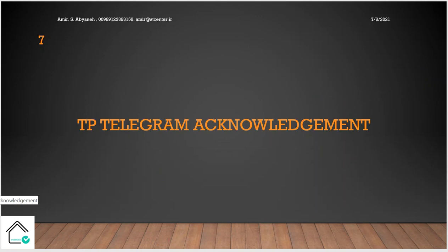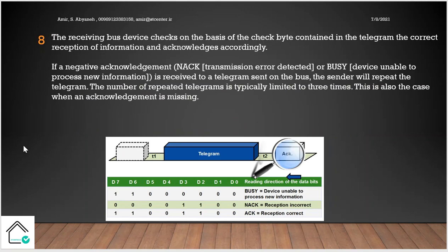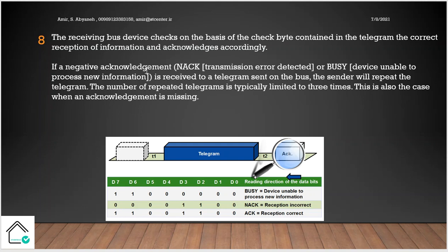We have the acknowledgement in transmission of the KNX. So because the KNX is like the TCP/IP, it's a two-way communication. When you send the data, you will receive the acknowledgement of the receiver. The receiving bus device checks on the basis of the check byte contained in the telegram the correct reception of the information and acknowledges accordingly. If a negative acknowledgement, not acknowledgement transmission error detected, or busy device unable to process new information is received to a telegram sent on a bus, the sender will repeat the telegram. The number of repeated telegrams is typically limited to three times.